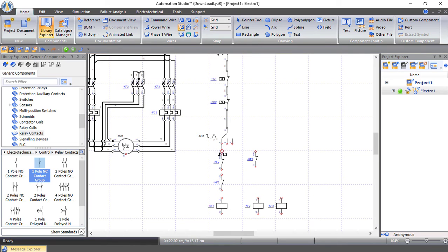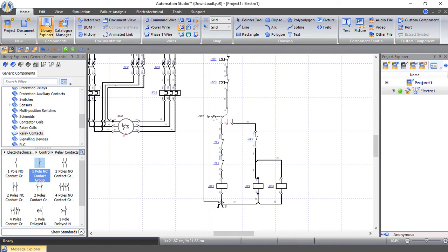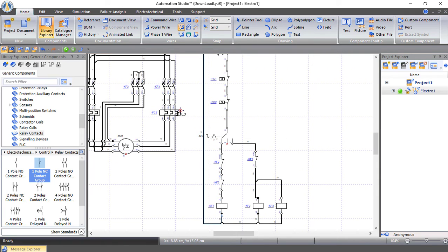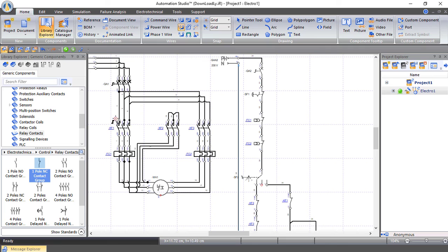Here from wires, let's connect the circuit. Also here we will connect the second position. Now this is connecting the neutral wires. Let's now connect the neutral to those wires. And now, as you can see, we are good to go. This is a complete connection for the Dahlander motor, the delta connection, which has the low speed, and the high speed connection, which is called star-star.